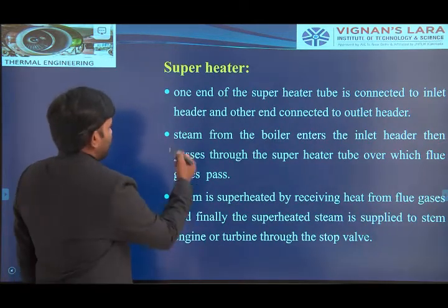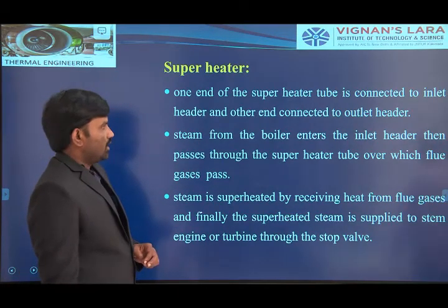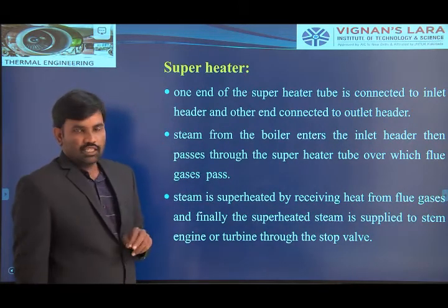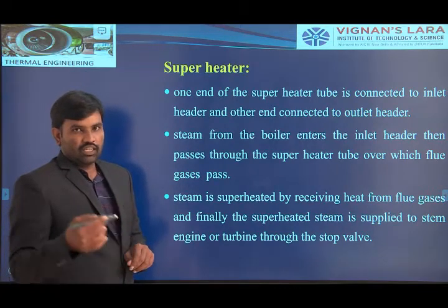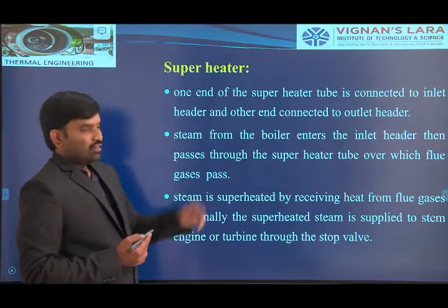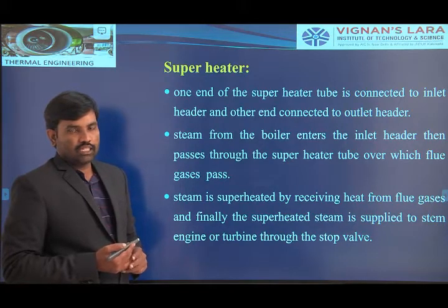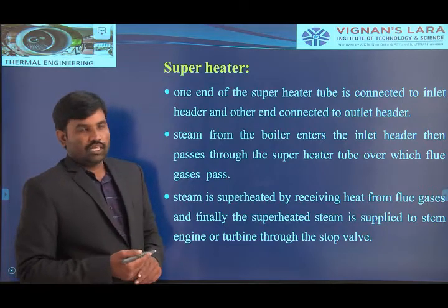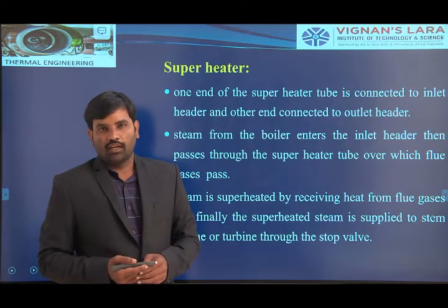In the superheater section, one end of the superheater tube is connected to the inlet header and the other end is connected to the outlet header. Inlet header means the inlet of the steam supply point from the boiler section. After generation of steam in the boiler section, we collect the generated steam at one end of the superheater tube, and during the circulation of the generated steam in the superheater tubes, we heat the saturated steam up to the superheating condition with the help of hot flue gases.